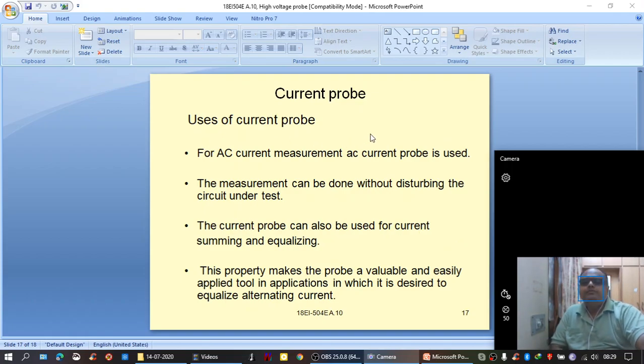Uses of current probe. For AC current measurement, an AC current probe is used. The measurement can be done without disturbing the current under test, the circuit under test. Particularly, these current probes are used for checking the current in live electrical wires that are running on poles. To measure the currents, these current probes are used directly without disturbing the circuit.